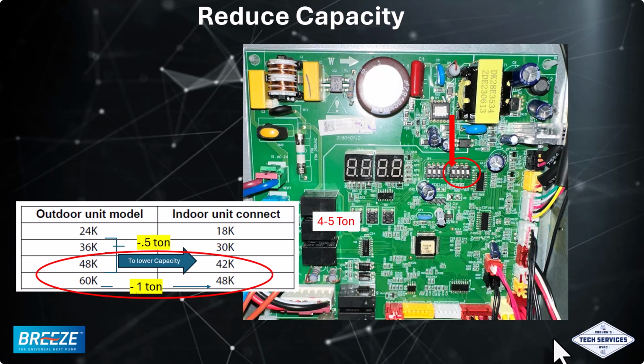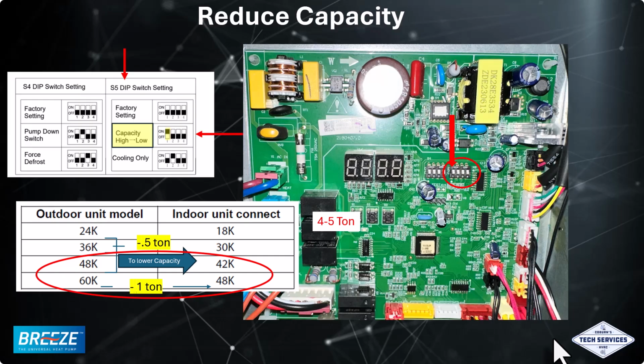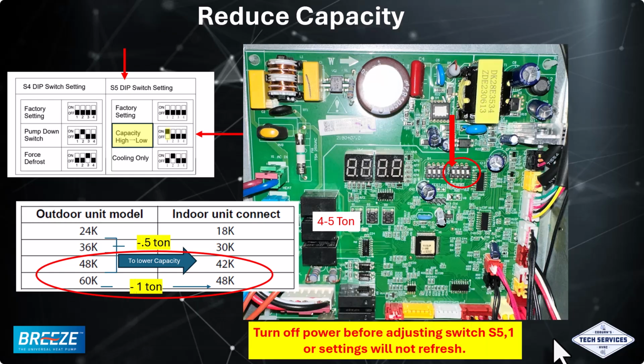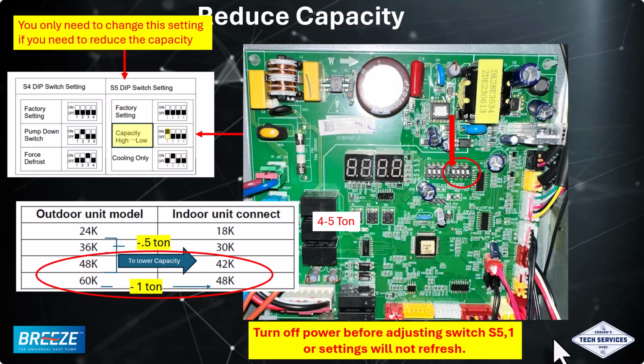Looking at the 4 and 5 ton unit, we will do the same thing. We're going to go to dip switch bank 5, switch 1, and we're going to turn that switch to on. That will reduce the 4 ton by 1/2 a ton and the 5 ton by 1 full ton. And be sure that the power is off before adjusting the switch. You only need to change this setting if you need to reduce the capacity.